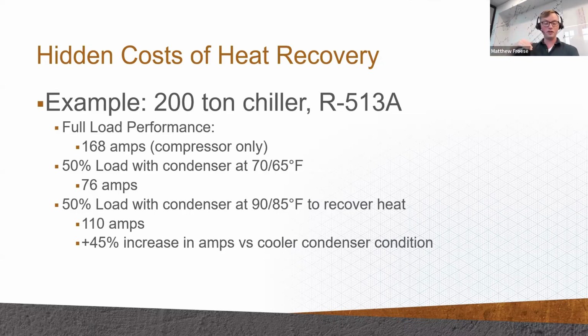The unit gets more efficient. But if we have to run the condenser side hot so we can recover that heat usefully mechanically elsewhere in the building, our compressor load goes up. And we go from, in this case, for this real piece of equipment, 76 amps up to 110 amps, 600 volts. So it's a lot of power. And it's a 45% increase in our compressor power demand.